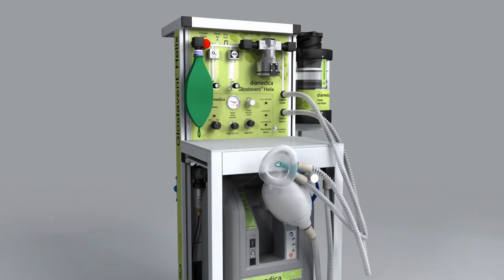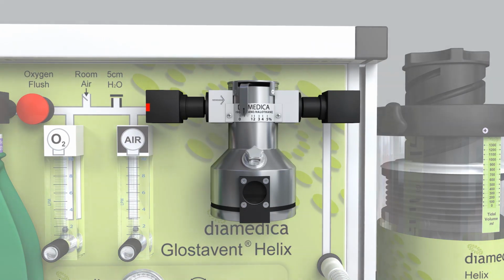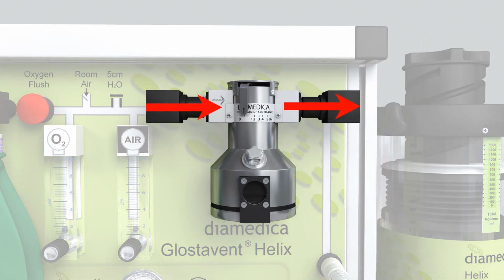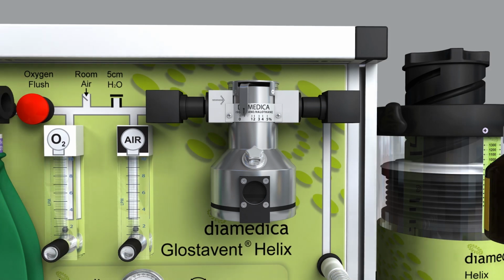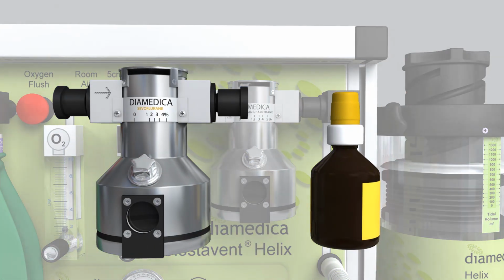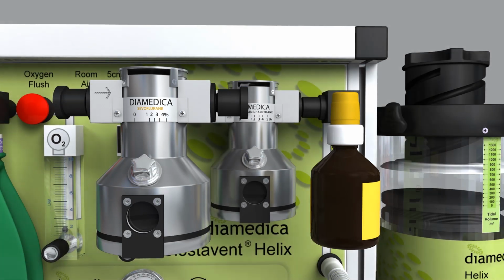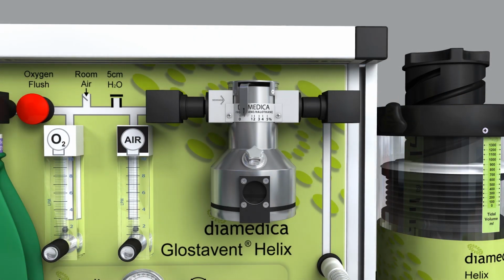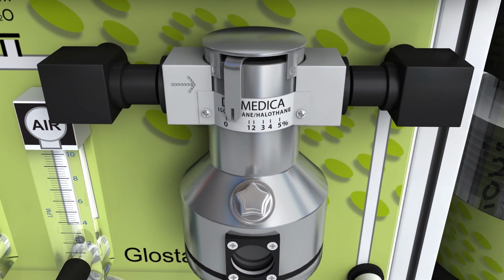The Glostavent Helix has a unique low-resistance vaporizer which enables seamless transition from continuous flow to draw-over anaesthesia. This vaporizer is suitable for isoflurane or halothane. Either can be used, but only one at a time. A separate vaporizer for sevoflurane is available on request. The vaporizer is thermally stable, ensuring a steady, controlled output of anaesthetic agent. The output is controlled by moving the lever across the front of the vaporizer.